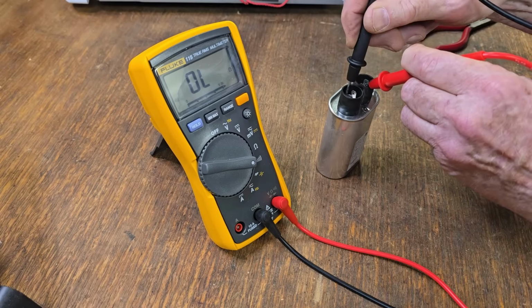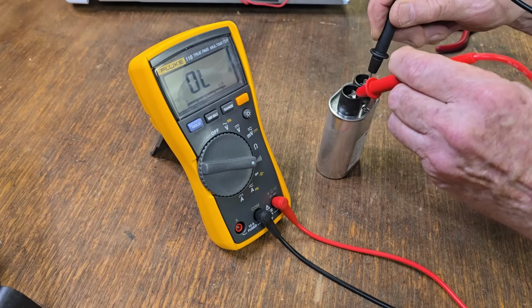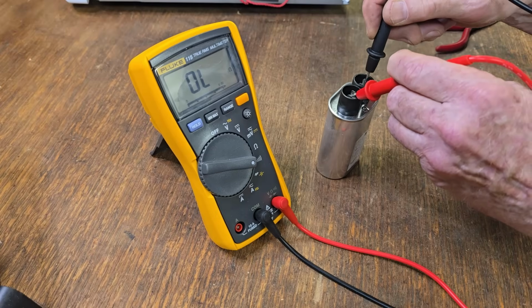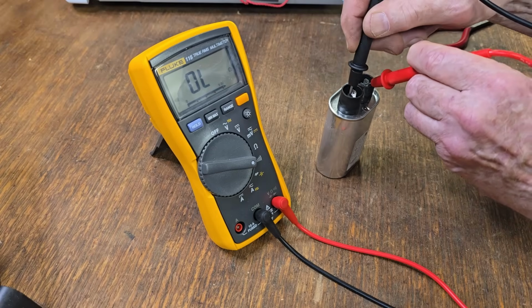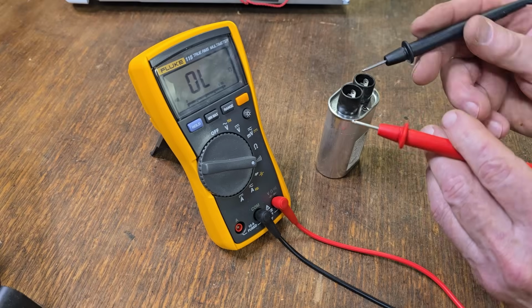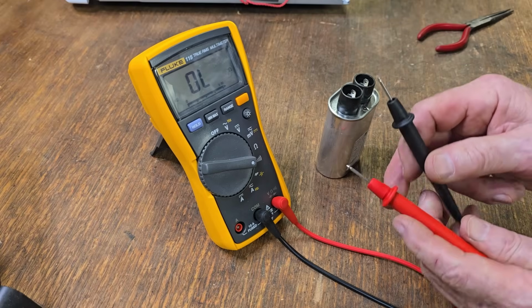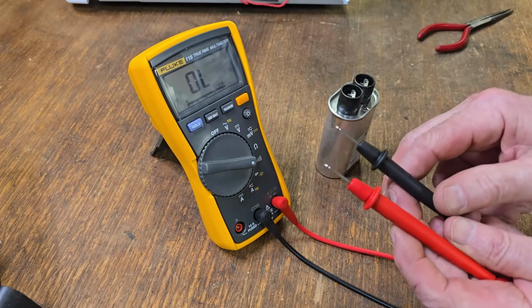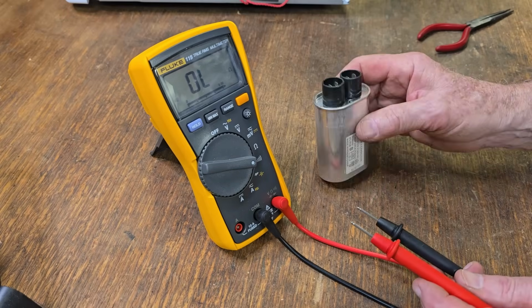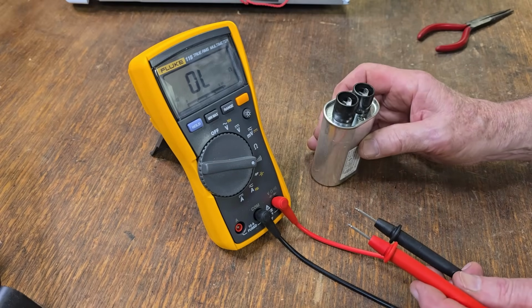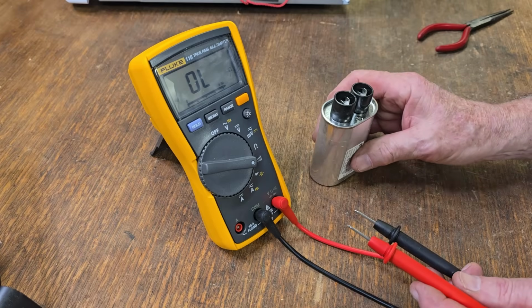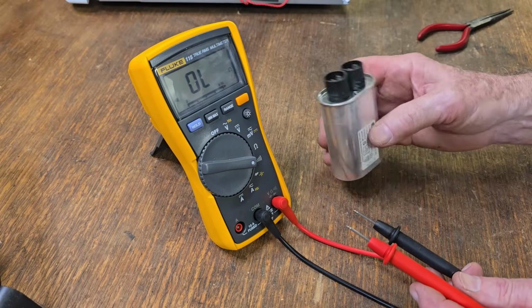That's all good, we had a bit of a beep there because it's accepting charge out of the meter. For the meter to do a continuity test, it has to put a bit of power down the leads, and it's charging just a whisker, that's why we get a bit of a beep. The moment we reverse it, we get a beep the other way, but that's fine. It seems to test okay.